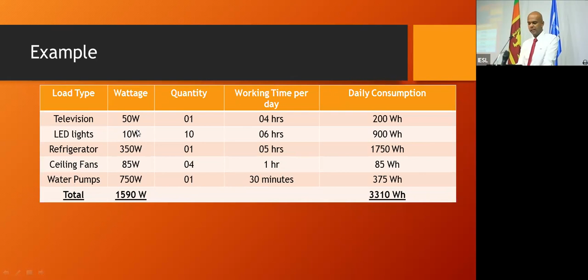So for example, if we want to size an inverter, are we going to buy a 1590 watt inverter? No, because inverters have something on their nameplate, but their continuous rating is different. So I always say multiply it by at least 25%. If you need 1 kilowatt, use 1.25, because at a high loading factor the inverter is going to get very hot and you're going to kill it very soon. So if it's 1500 watts, try and use maybe a 2.6 kilowatt inverter.